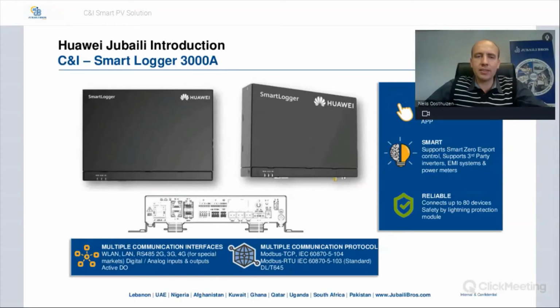Or if you're adding additional devices like weather stations or power sensors, for each power sensor taking up a slot, you can reduce the inverter. So if you've got one power sensor and one weather station, it means you can only add 78 inverters. But I mean, if you're looking at 100 KTL times 78, it's quite a large system that you can install.